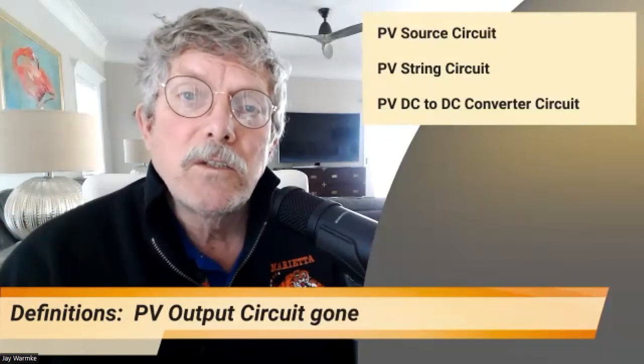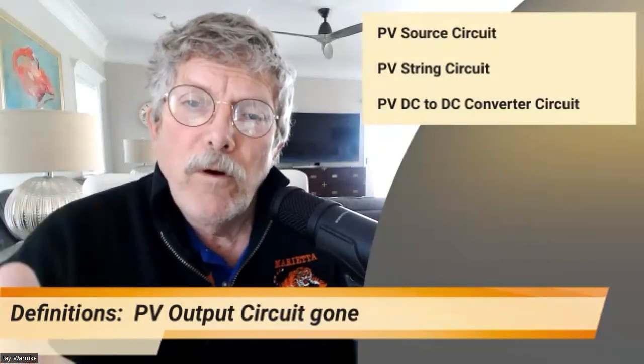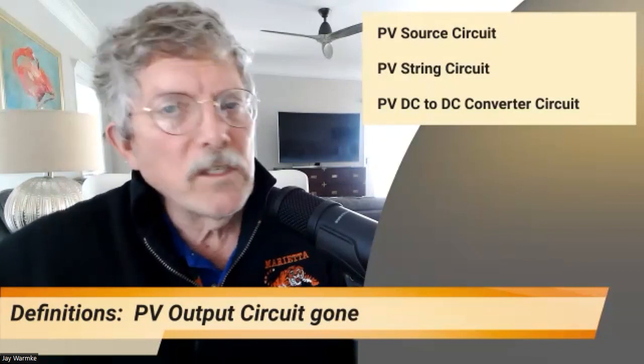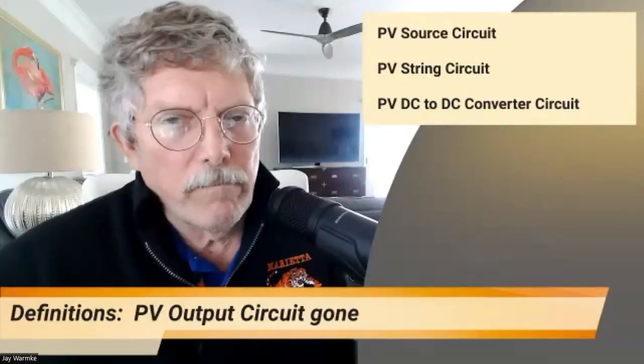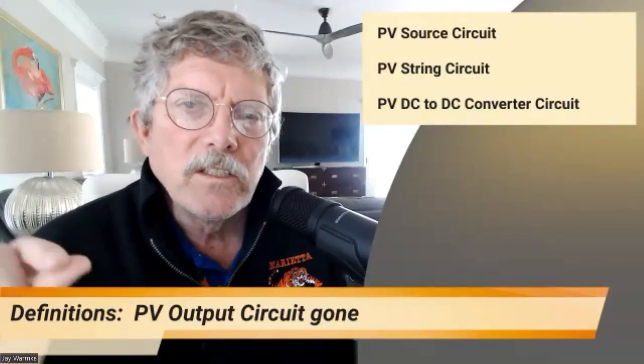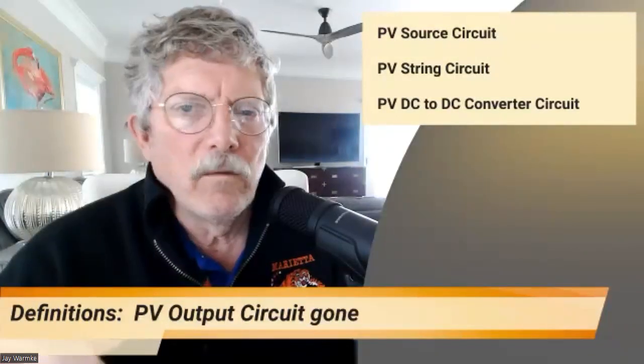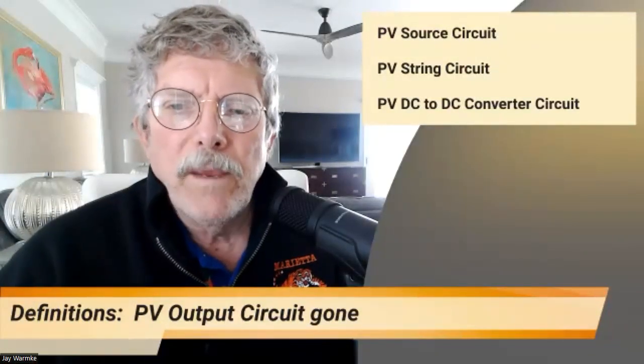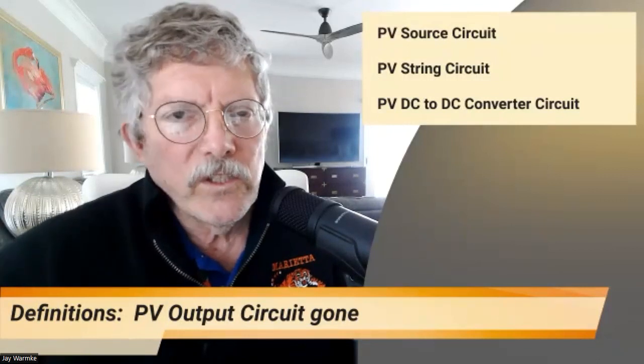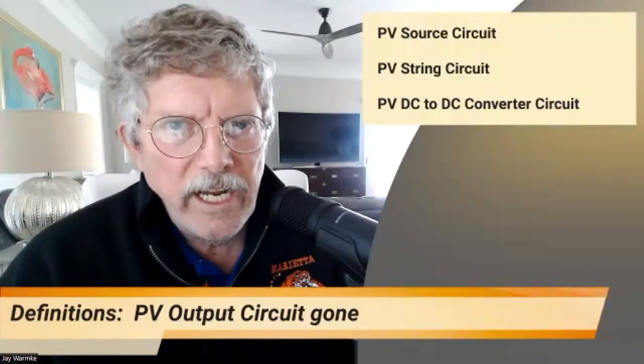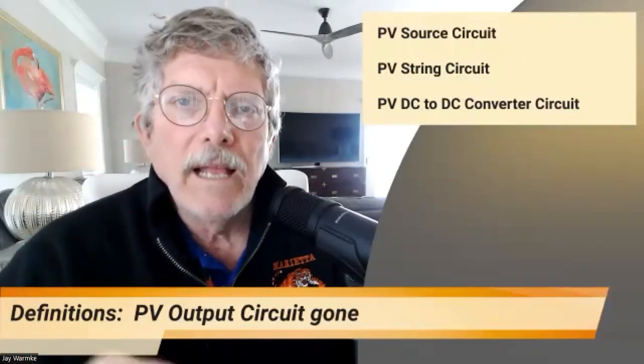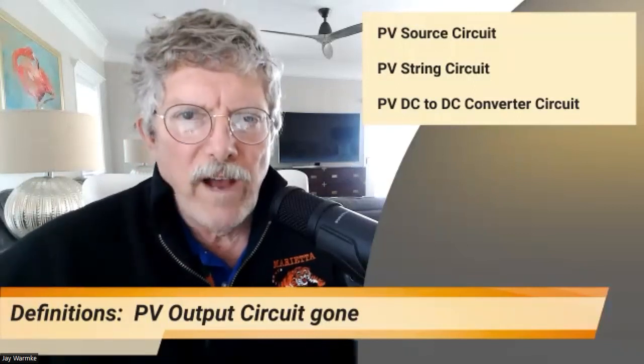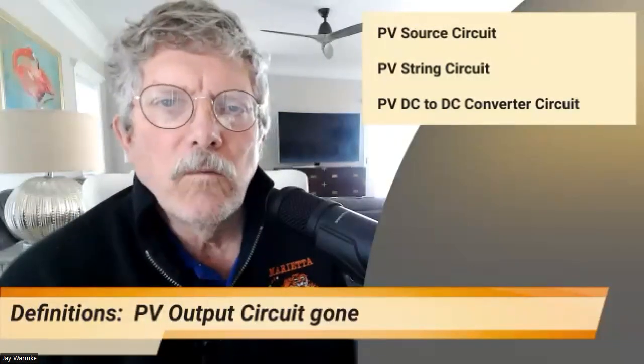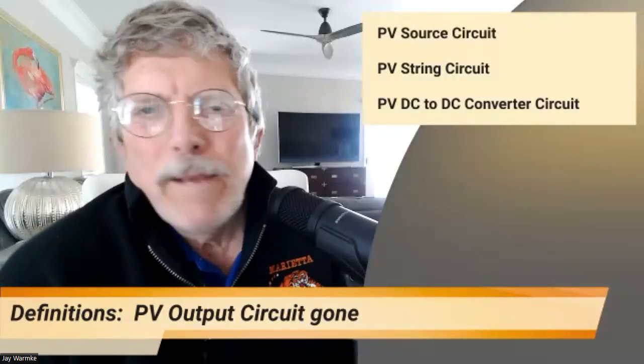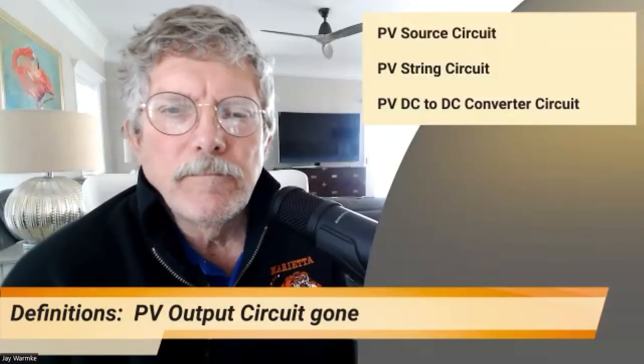But if it's connected to a power optimizer, from that point forward, all of the fluctuations are dealt with by the electronic device. So that is no longer a wild circuit. It will not fluctuate. So the PV DC to DC converter circuit is being differentiated, because now you would not put that second 1.25 multiplier when you're sizing the wire. So they're just making it a little more confusing, but I guess there's a rationale behind that.